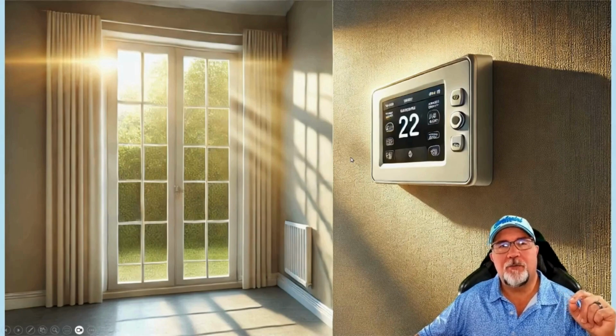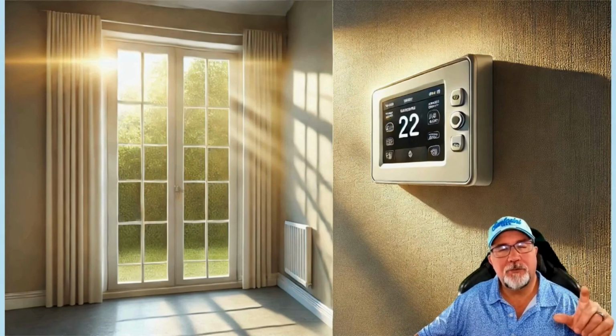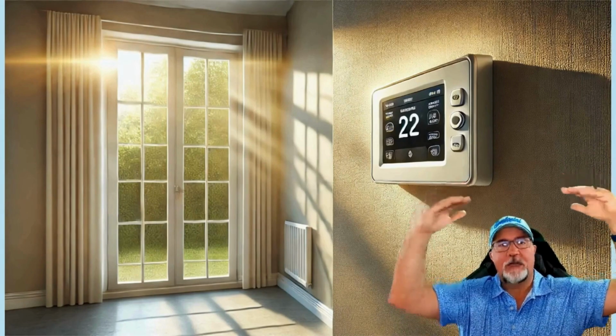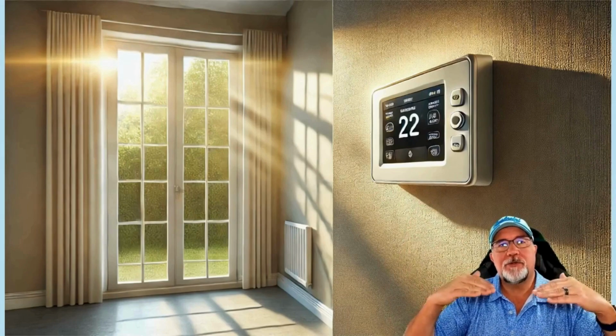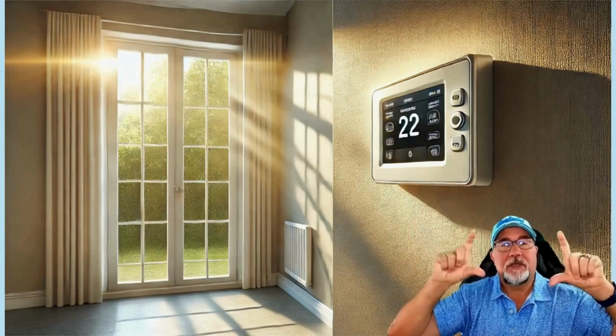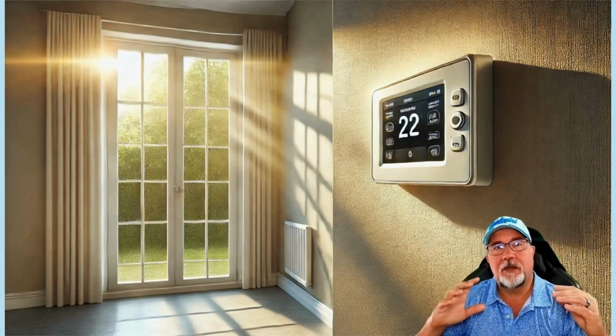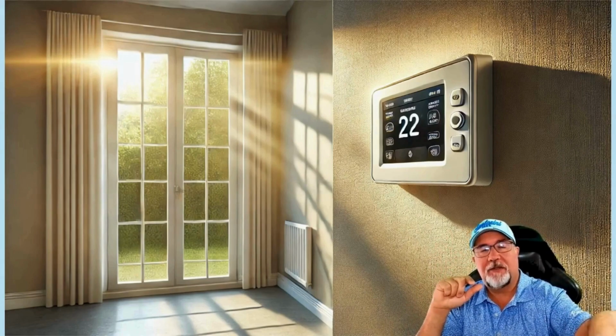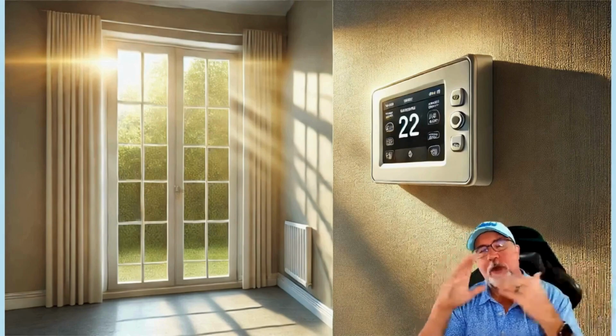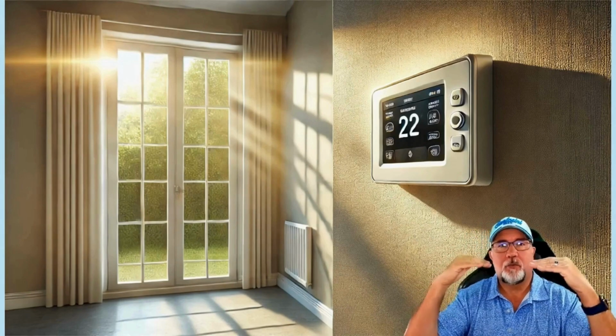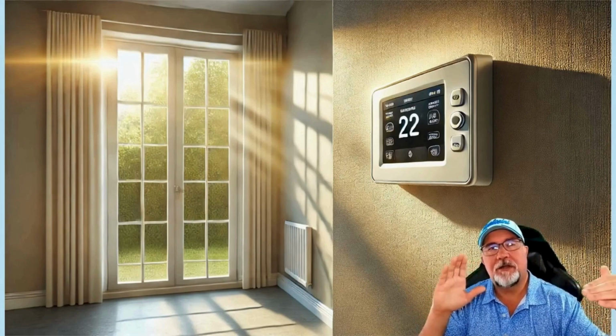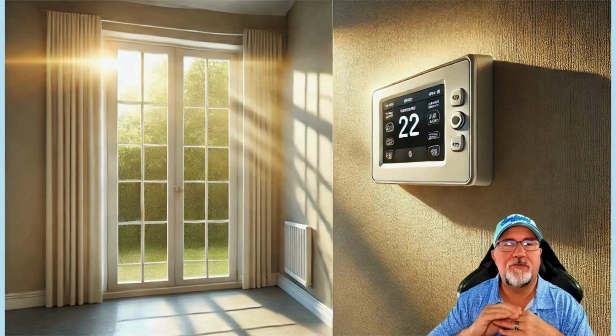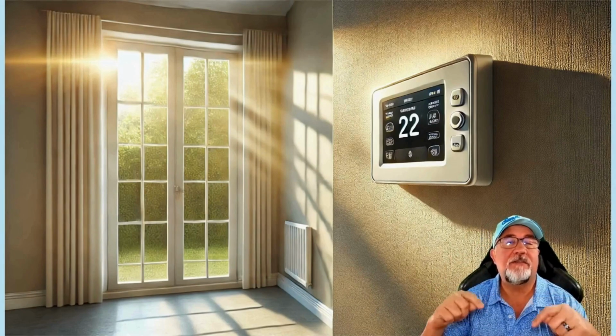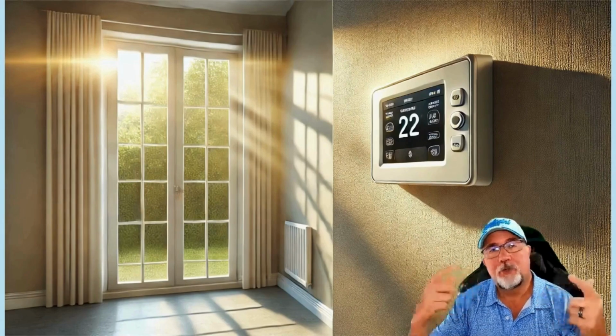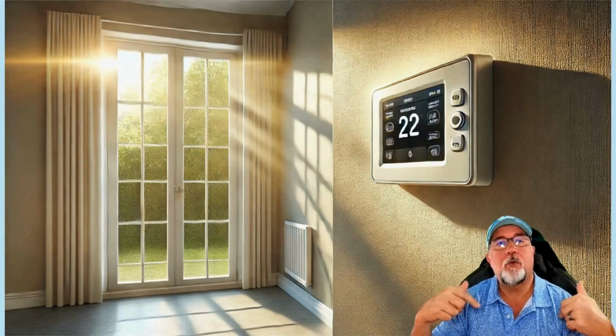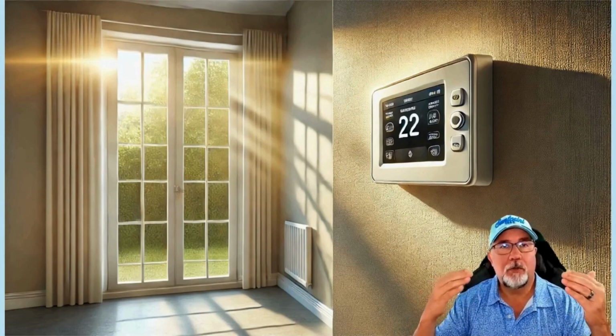When you're placing the thermostat, one should be close to the main return that the air is going in, so it can properly determine the temperature of the air going into the unit and keep it consistent. Because if you have the thermostat in a location that has a lot of heat bearing on it, like you see here, we've got sunlight coming in from that window shining right on that thermostat. Now, even if that thermostat is directly under the return, the sun and the rays are actually going to increase the air temperature in front of that thermostat, and it's going to make the thermostat think that it's hotter than it actually is, which could cause the unit to run longer and cool the house down in certain areas lower than it should be.